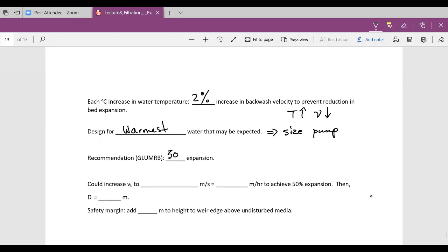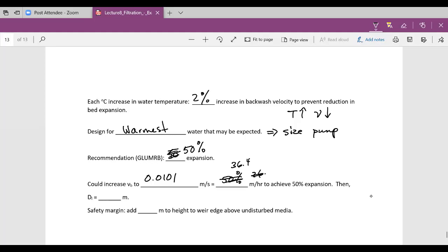We want 50% expansion. If we increase our backwash velocity from 0.01 to 0.0101 meters per second, we would achieve 50%. That equals 36.4 meters per hour, achieving 50% expansion with a bed depth of 0.749 meters. So very small changes are needed to go from 45% to 50%.